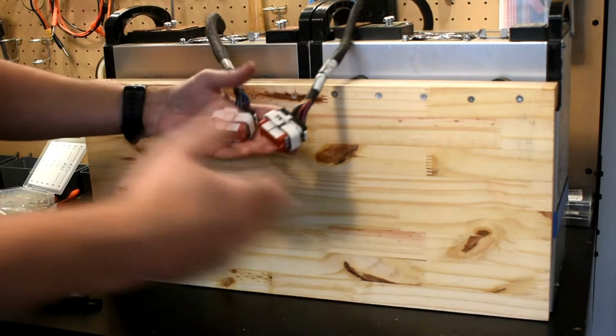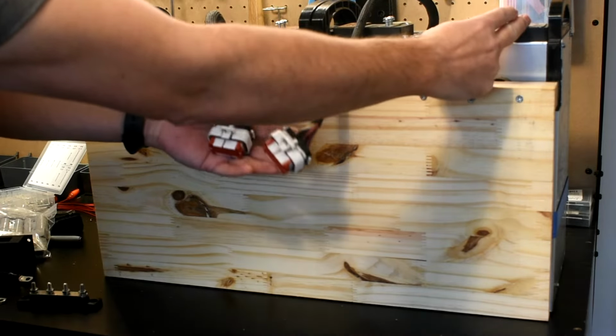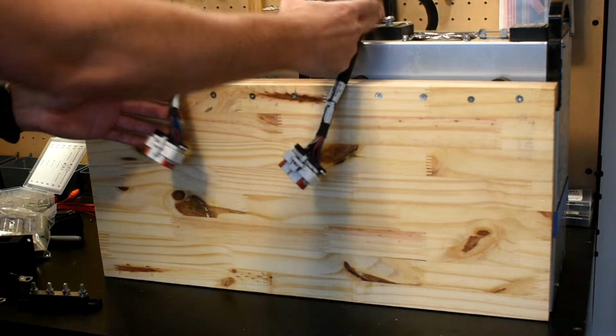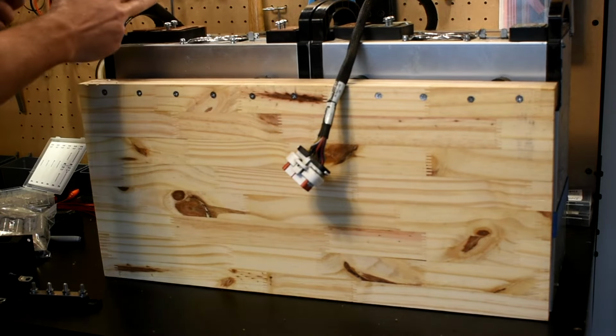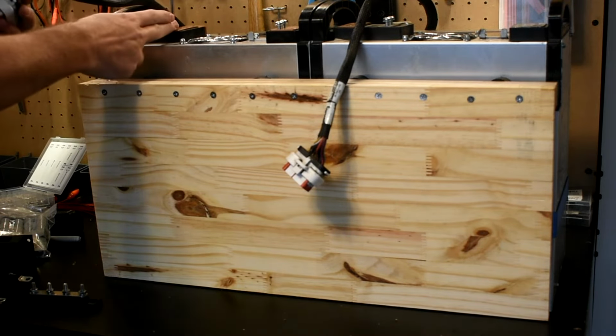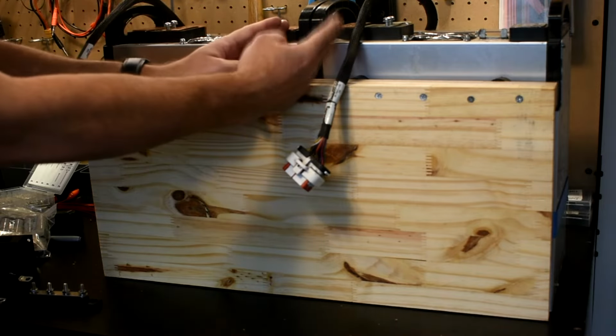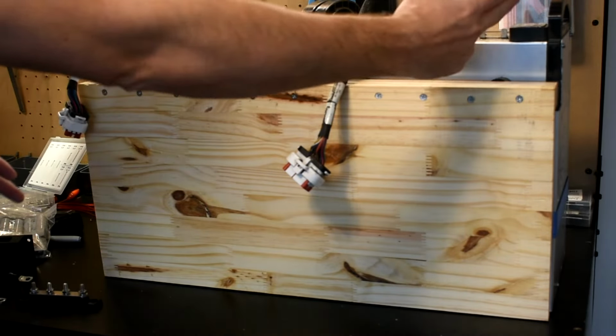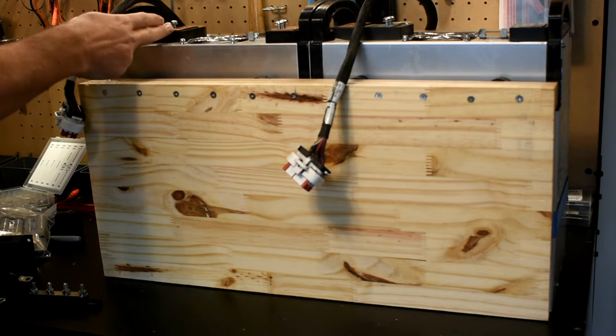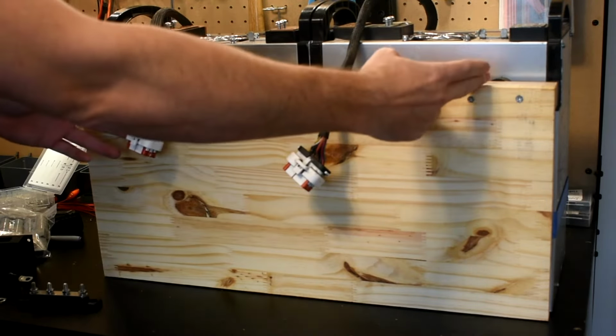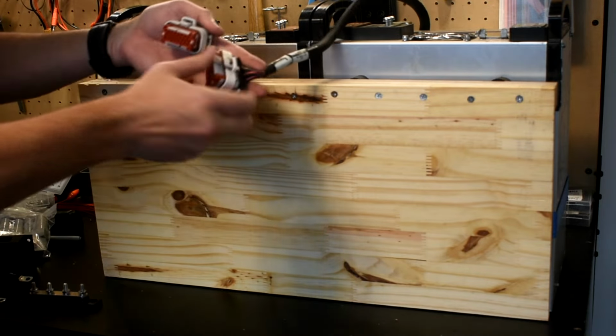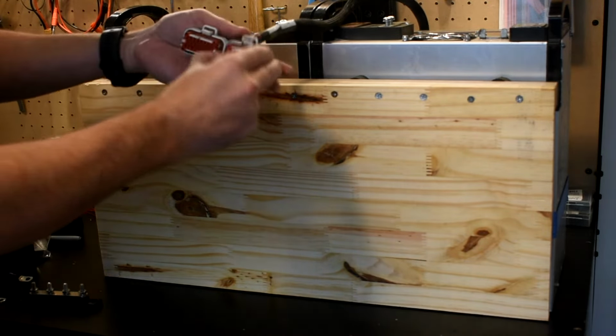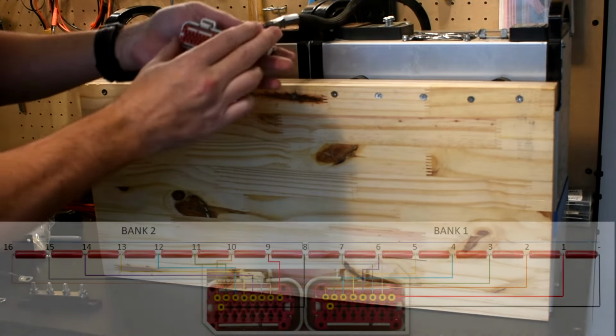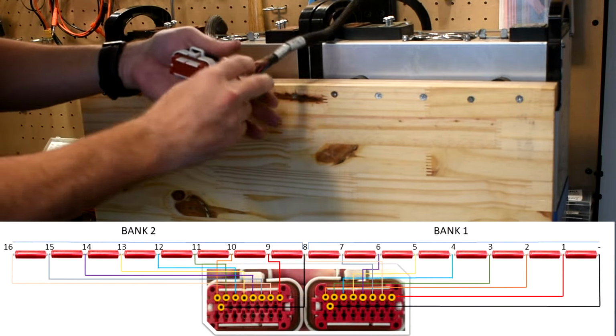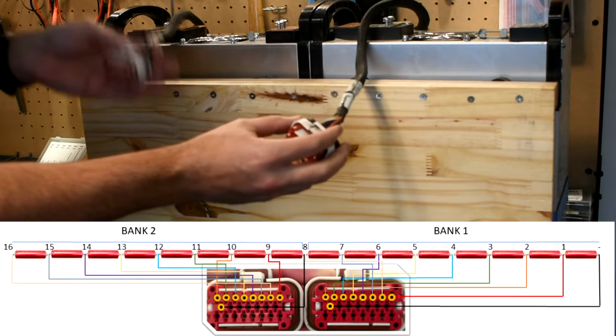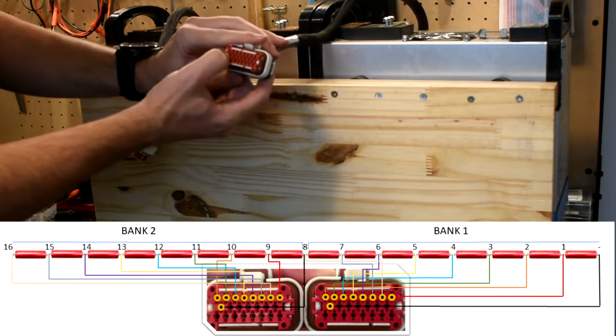Think of it this way: here is a ground spot, and then a positive spot here, a ground spot here, and a positive spot here. What we're going to do is bridge these two, creating a flow from ground all the way to positive. Each one of the segments in these batteries has a lead wire coming from these pins. They have a diagram on batteryhookup.com showing where each position is. I consider this bank 1, and this bank 2. So we're going to start at this, which is ground.